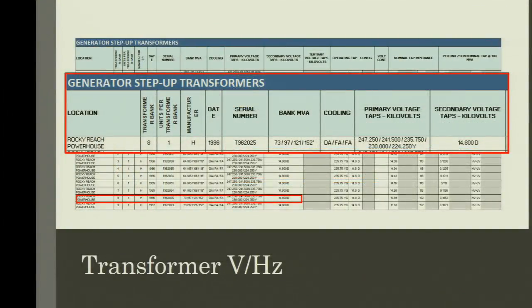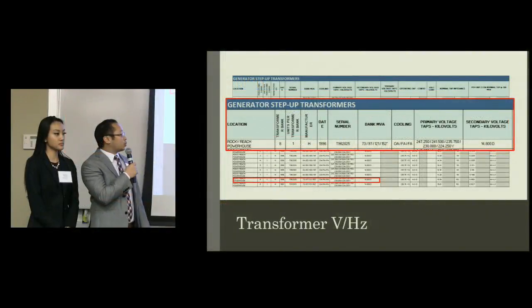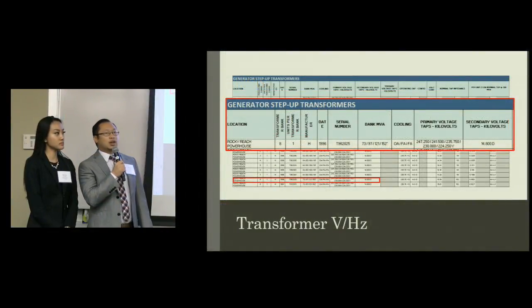If you look at the last value in there, 152 MVA is the transformer rating when it is operating at 65 degrees Celsius. This is the rating we'll use because when talking about limits, you want the greatest known rating of the transformer.